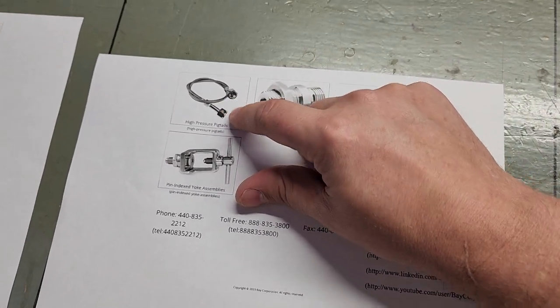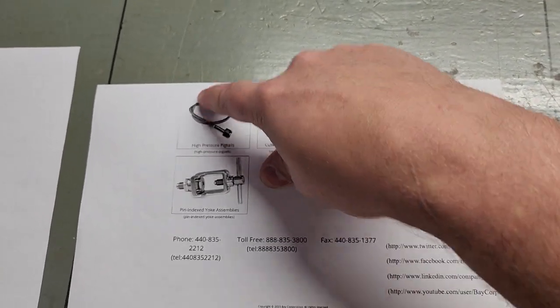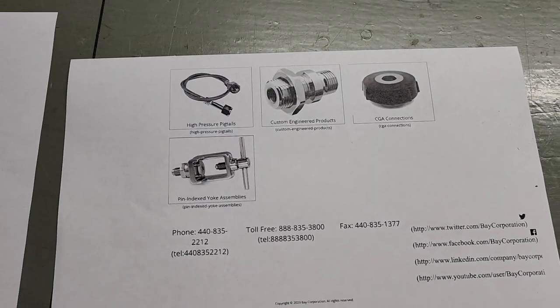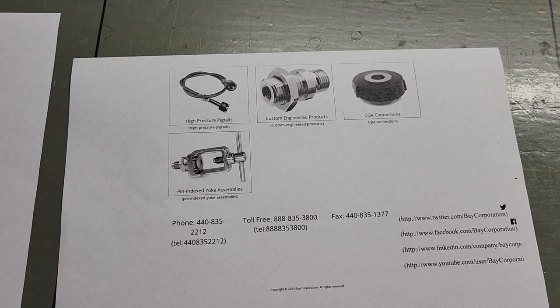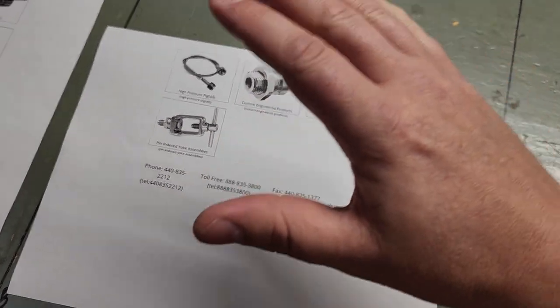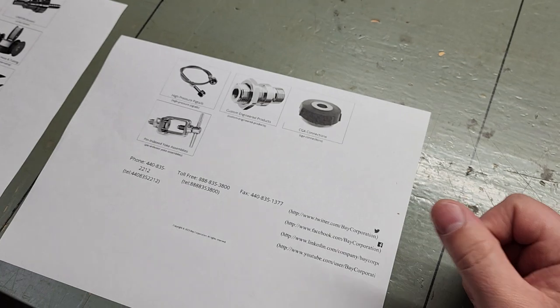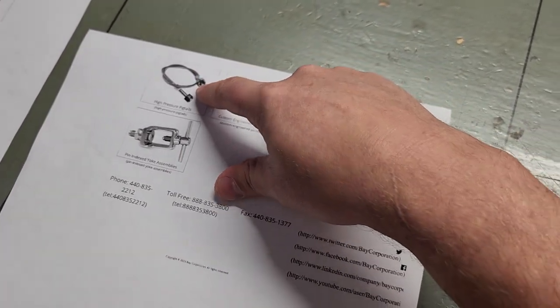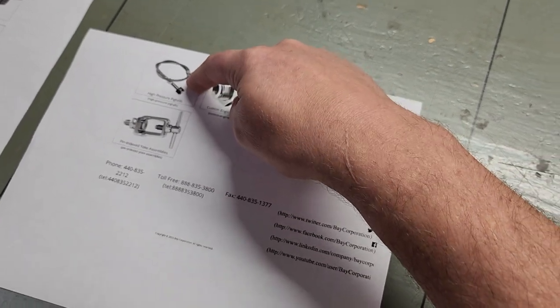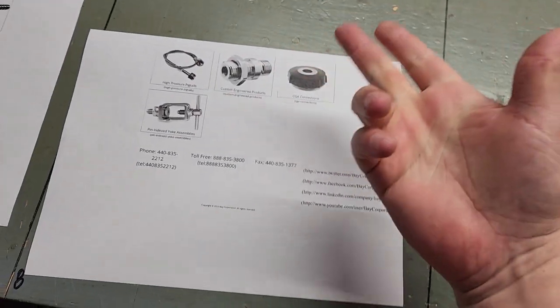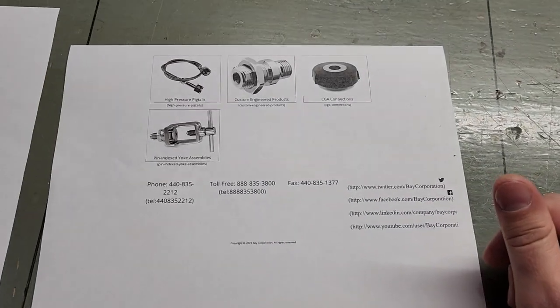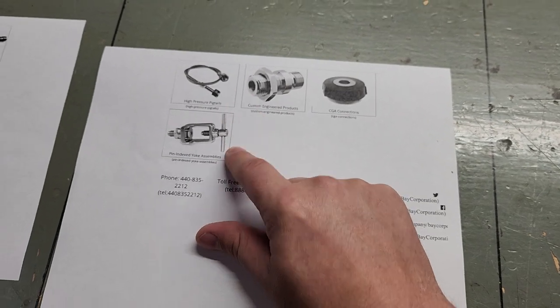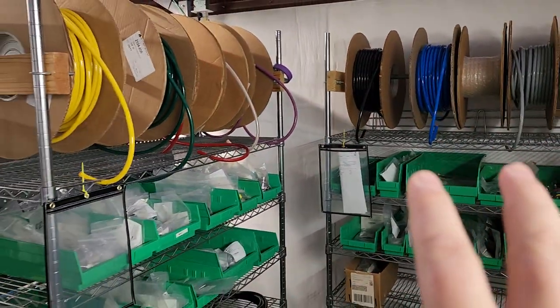Compressed gas fittings for high-pressure hoses have a stainless steel exterior that's abrasive-resistant and handles high pressure like bottled carbon dioxide. Most hoses here are for wall gas with strictly regulated pressures, but bottled gas—oxygen, nitrogen, carbon dioxide—has much higher pressures. We also handle a variety of different yoke assemblies.